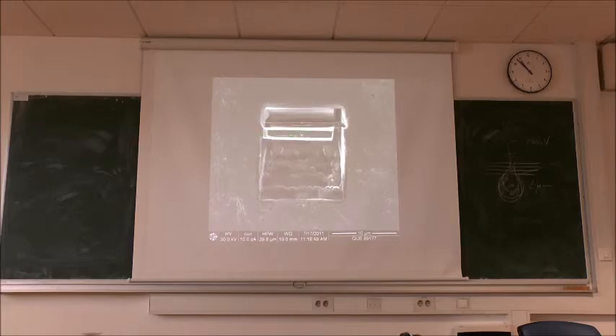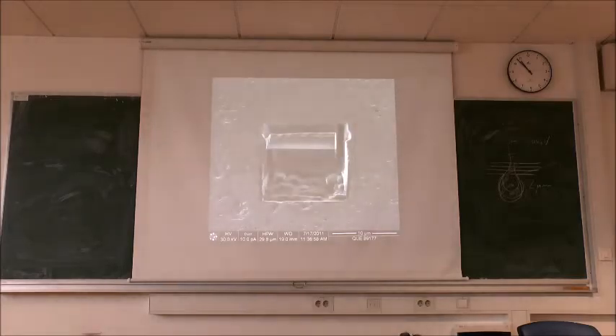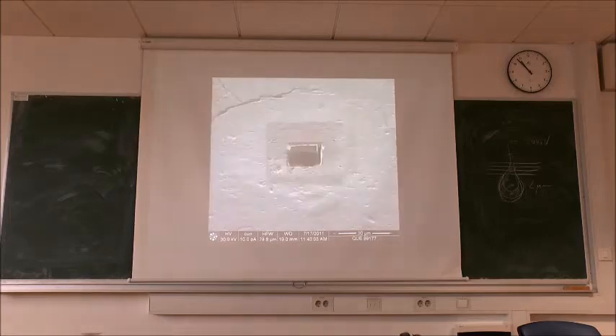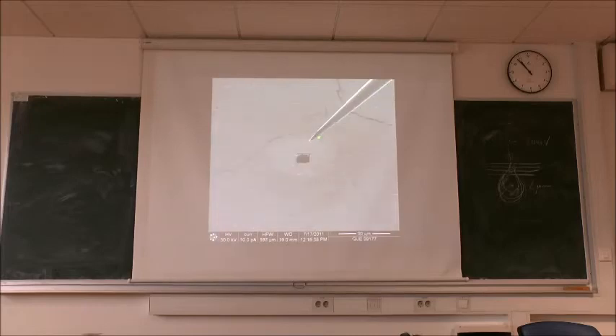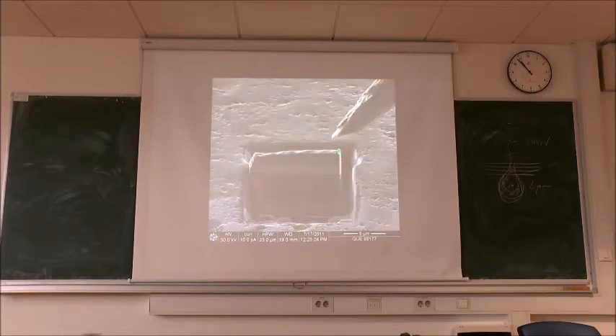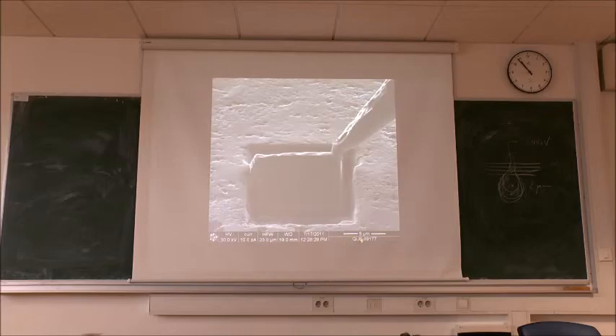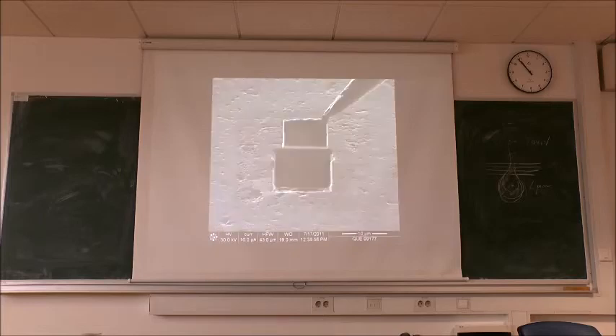You see, it's fixed just on this part. This is platinum. You can then use fine thinning, fine milling on this part and another part. You can thin it, but not down to the extreme, because the next part could resemble a Greek tragedy, since this is the most critical part. You see, the size of this is very small. This is micro-manipulated, and you should bring the micromanipulator just a few tens or hundreds of nanometers, and you weld it here, you cut it there, and you get a lamella. Very easy, huh?